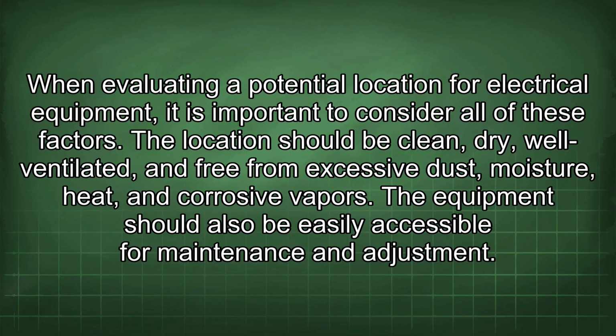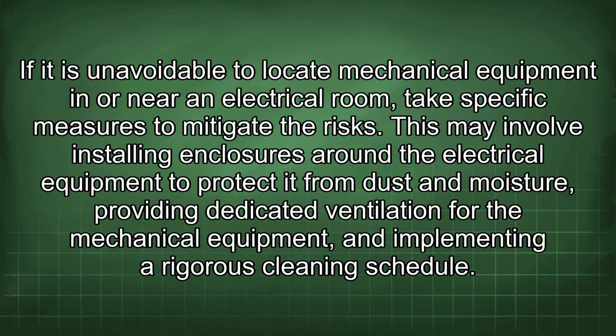When evaluating a potential location for electrical equipment, it is important to consider all of these factors. The location should be clean, dry, well ventilated, and free from excessive dust, moisture, heat, and corrosive vapors. The equipment should also be easily accessible for maintenance and adjustment. If it is unavoidable to locate mechanical equipment in or near an electrical room, take specific measures to mitigate the risks. This may involve installing enclosures around the electrical equipment to protect it from dust and moisture, providing dedicated ventilation for the mechanical equipment, and implementing a rigorous cleaning schedule.